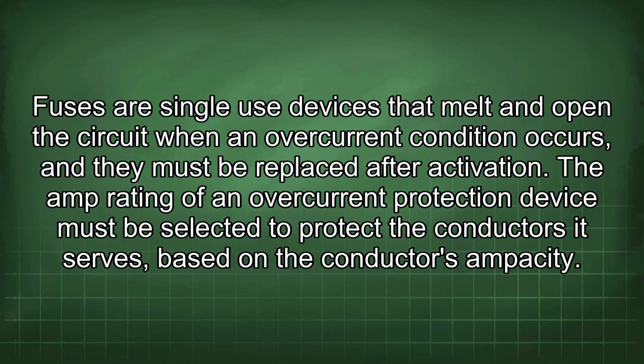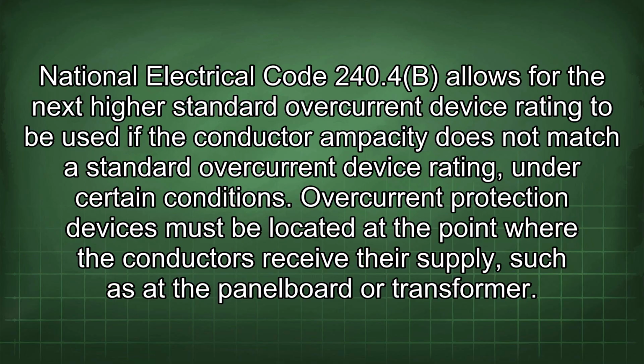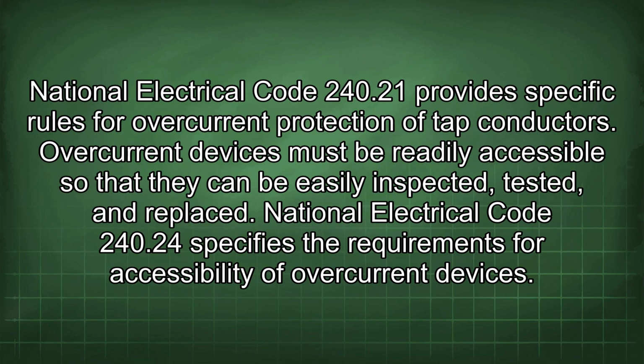The amp rating of an overcurrent protection device must be selected to protect the conductors it serves based on the conductor's ampacity. National Electrical Code 240.4(B) allows for the next highest standard overcurrent device rating to be used if the conductor ampacity does not match a standard overcurrent device rating under certain conditions. Overcurrent protection devices must be located at the point where the conductors receive their supply, such as at the panelboard or transformer. National Electrical Code 240.21 provides specific rules for overcurrent protection of tap conductors.